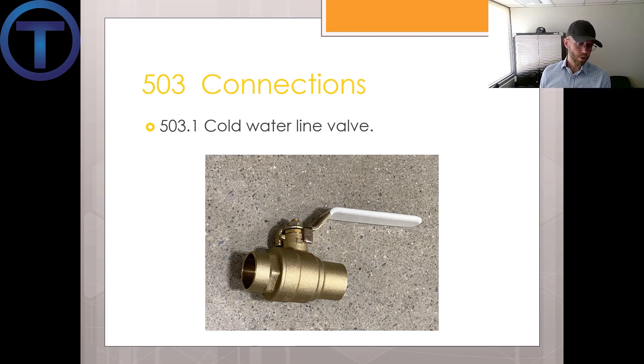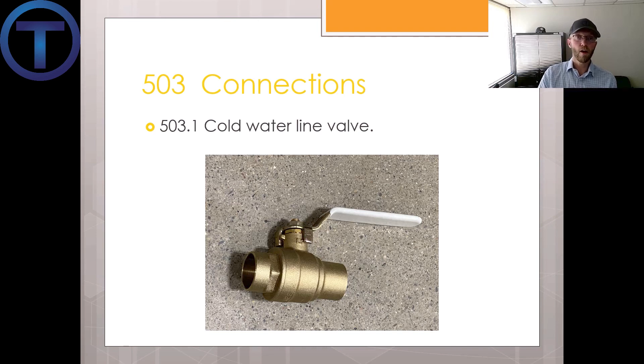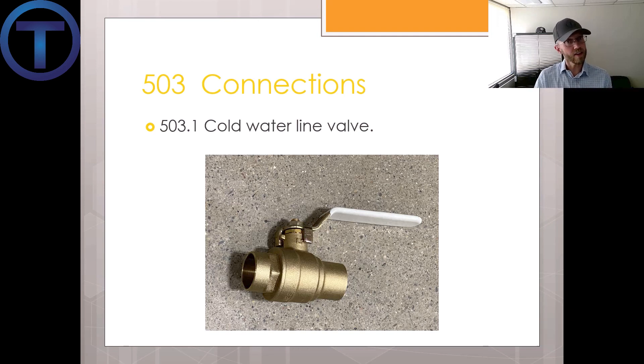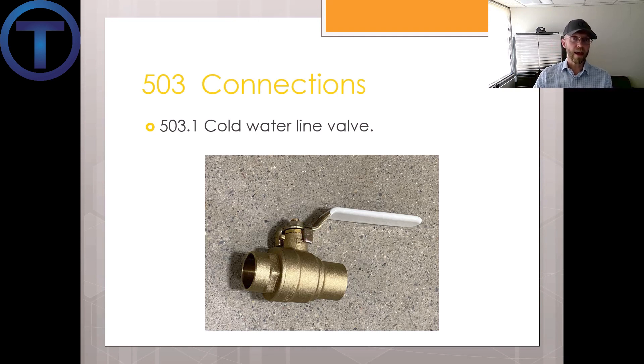503.1 covers the cold water line valve and states that we need a shut-off valve for the water heater on the cold side. You can put one on the hot side as well — that's good for service — but at a minimum you should have one on the cold side, and it has to be dedicated to that appliance.